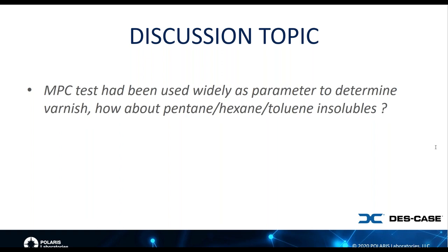I was going to add that yes, there is specific testing for picking up pentane, hexane, and toluene insolubles, but they're not commonly used, just like Mark was saying. But we do have that capability. Laboratories will have that capability, not all of them, but some will. But they're not normally used. In fact, I haven't seen one in a while being tested for those. They're particular for oils that have to be really, really clean, like turbine oils. So they're not used commonly.